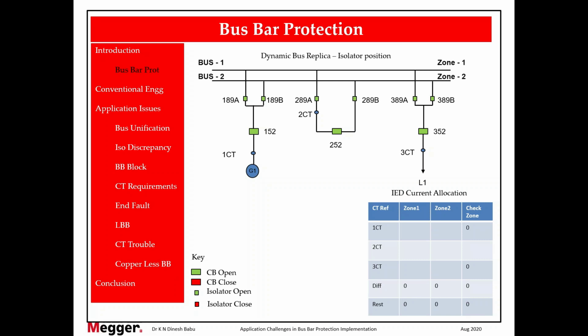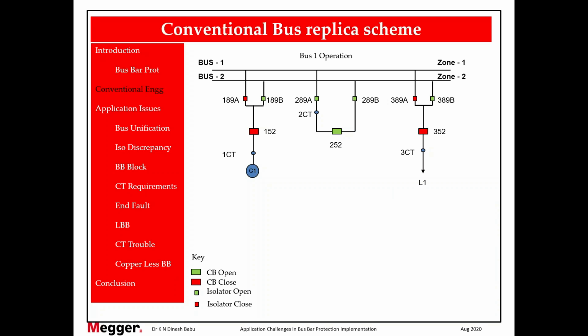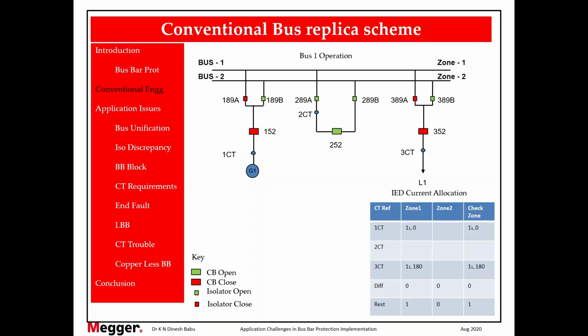So let's move on, operate some isolators and breakers and see the current flow direction. Now I have closed isolators 189A and 389A. Bus coupler is open. 152 and 352 are closed. So I am going to allot in this manner. The relay will read like this. 1 CT, 189A is closed, so it will read in zone 1. 3 CT, 389A is closed, so that will also read in zone 1.